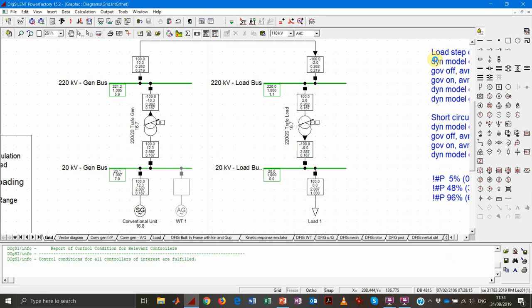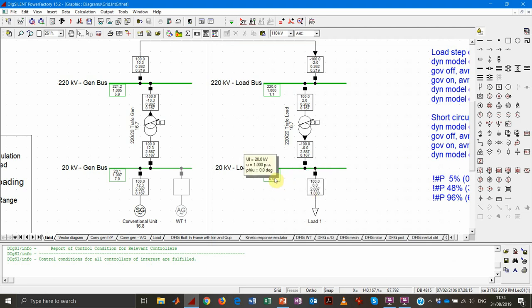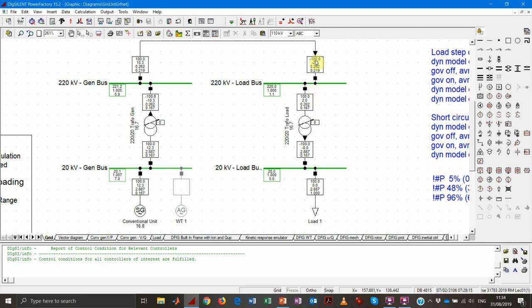We perform our load flow and the results are displayed. The load is consuming 100 megawatts, as expected, with no reactive power. Voltage at this bus is one per unit, because the generator is maintaining this voltage at the dispatch value, and the angle is zero because that's our slack. Going backwards, the active power at all measurement points — transformer, lines — is always 100 megawatts, since we have no resistive elements and thus no active power losses.